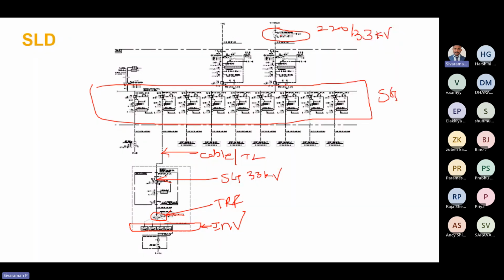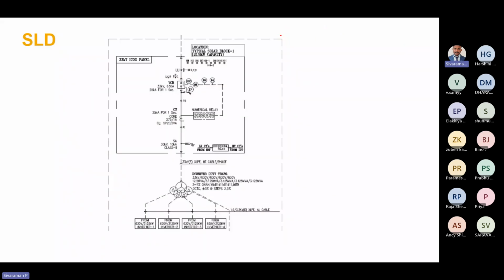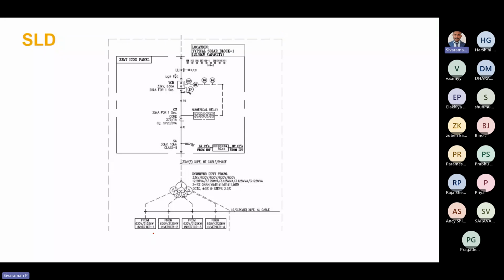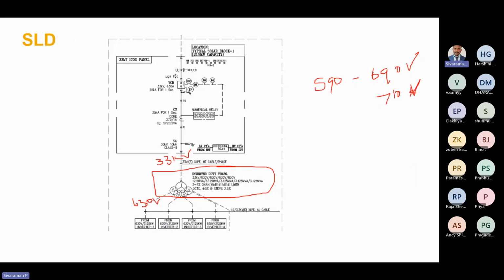Based on the power rating, the transformer rating will be there, right? So this is the clear view of it. Here you can see the inverter duty transformer. Its primary voltage on this side is 33 kV, and on the inverter side it is 630 volt. Most of the central inverters are available in the voltage level of 590 volt to 690 volt, or sometimes even 700 or 710 volt. That is based on the power rating and the inverter manufacturer. This is a 5 winding transformer. One primary winding will be there and 4 secondary windings will be there. That is the LV winding. Each LV winding will be connected to an individual inverter like this.